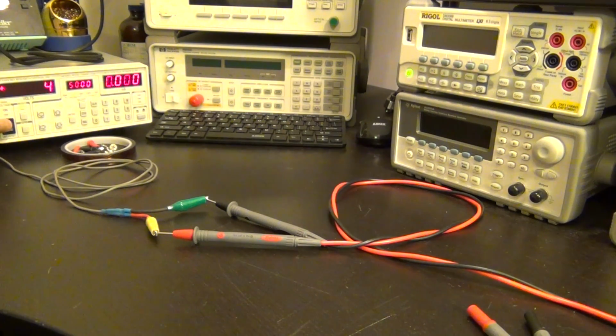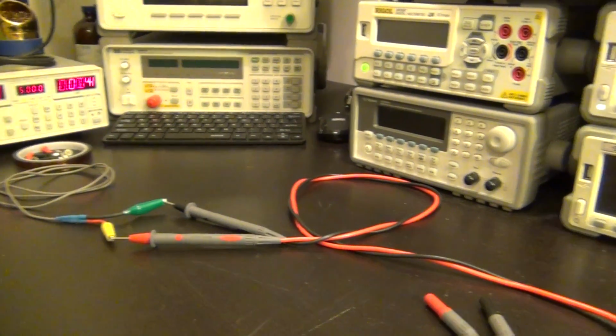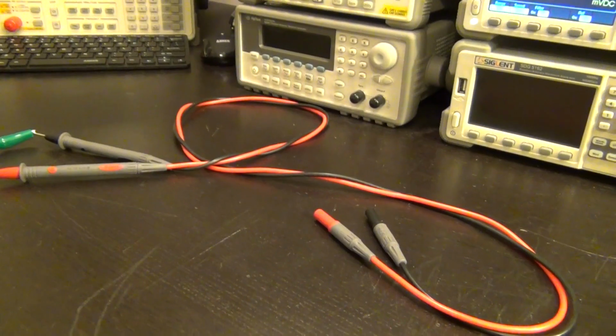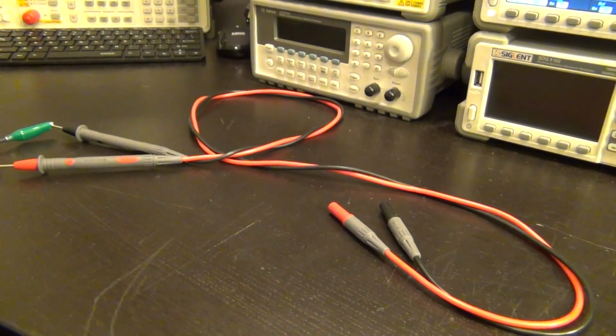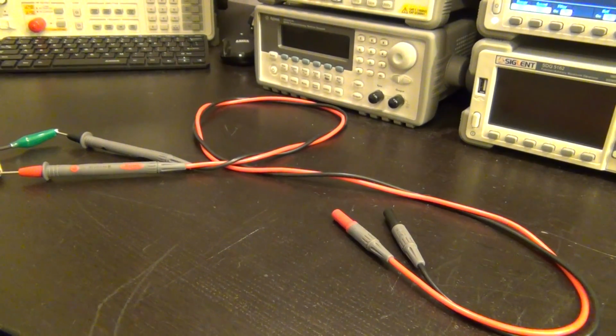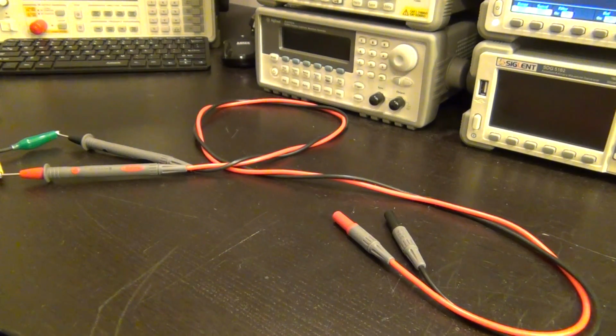We'll go ahead and enable that. There we go, and here's 5000 volts on that cable. The cable is wrapped together, and I see no dielectric breakdown. It behaves quite well, maintaining 5000 volts across it. The cable is quite nice and safe, so I wouldn't be worried about it.